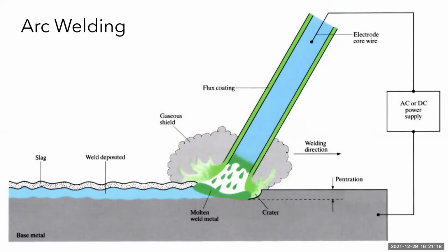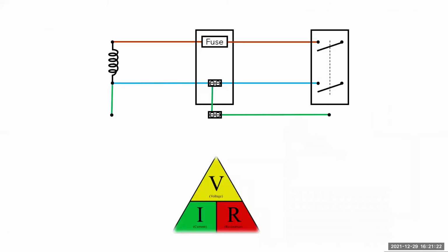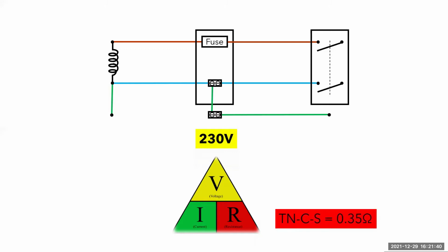So how much current would it take to do that? Well, here is a quick look at the supply current to give you an idea of why we need to protect people from electricity. We will cover this in more detail in the subsequent videos as we work our way through the testing process. But as you can see here, I've used 230 volts as my baseline voltage, along with a TNCS earthing system, which the on-site guide suggests should have a maximum external resistance of 0.35 ohms. The lower this figure is, the higher the potential current that is available in a fault condition. We then divide 230 volts by 0.35 and we get a current of 657.14 amps, or roughly 0.66 kA on your multifunction tester.